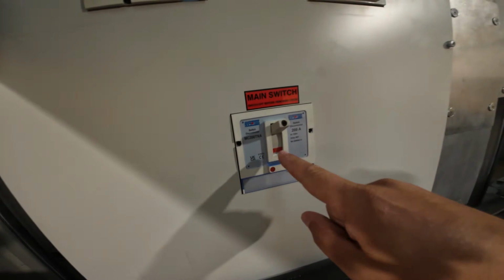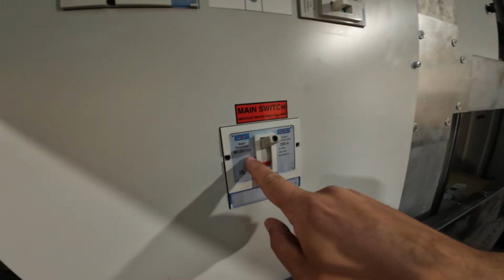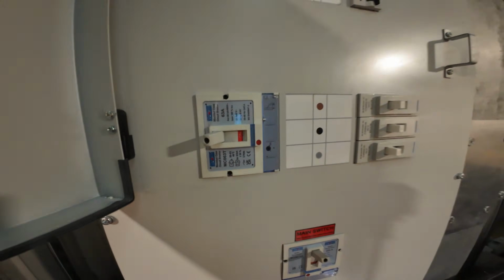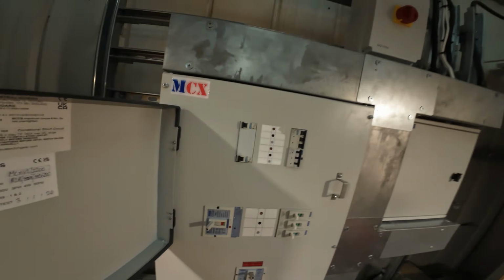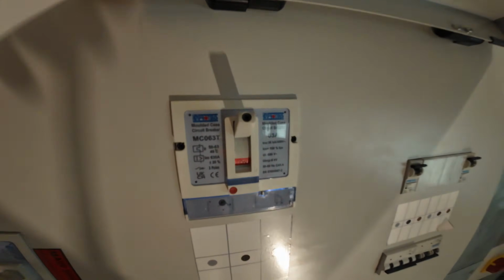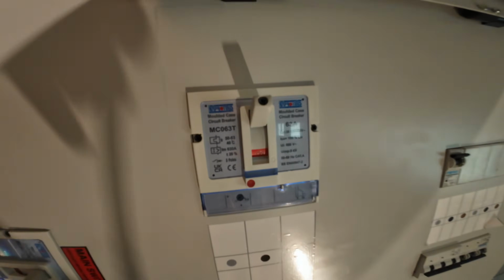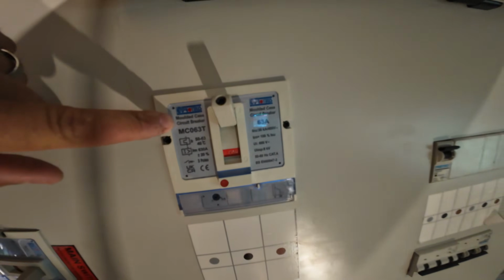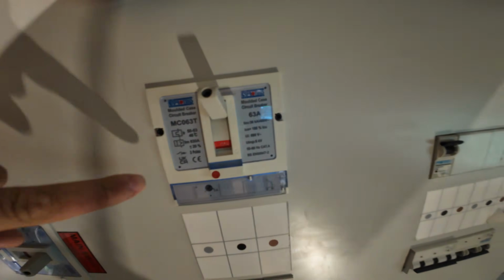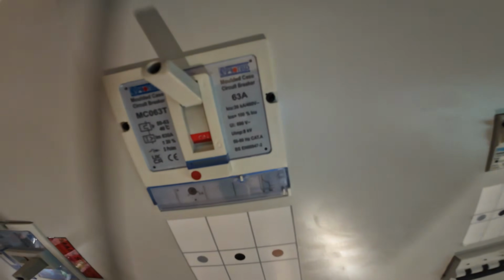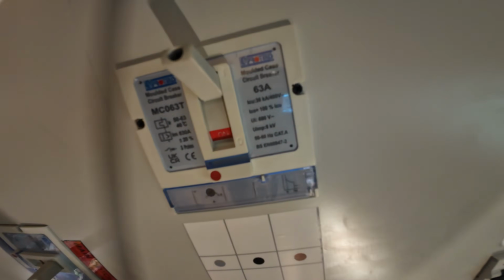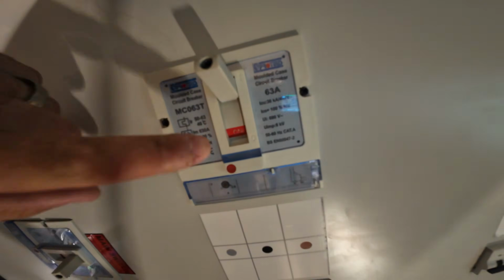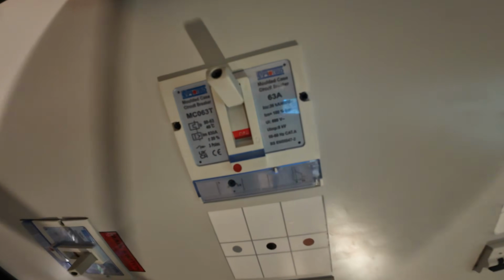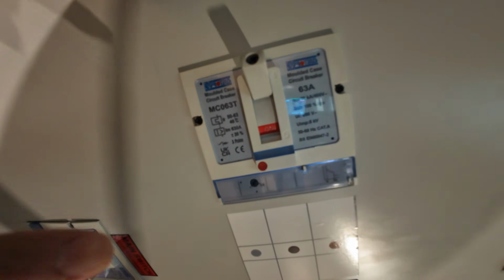This bigger one here looks the same, very, very similar. You can see this is an MC200 TNA switch disconnector. This one is a molded case circuit breaker. Let me spin the camera around so you can have a better look. We've got a molded case circuit breaker, and this is a 63 amp variety. You'll see on here it's BSEN 60947-2. Now that's important because that, among other things, relates to your pollution degree categories as well.